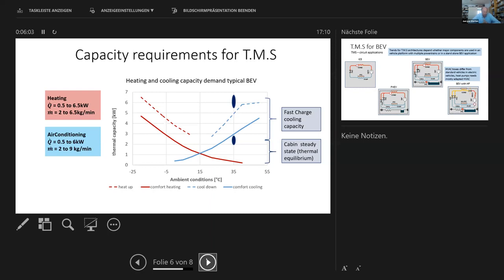Here values range from 6.5 kilowatt at -20 down to 0.2 kilowatt, which is a challenge for the compressor, with air mass flows from 30 grams per second to 110 grams per second. The heating capacities between about 5C and 40C are particularly problematic for the EV, as the air is often air conditioned and then electrically heated for comfortable blowout temperature. These operation points show an energetic advantage of the heat pump, as in the mode of cooling, sufficient heat is available due to compression and heat absorption.